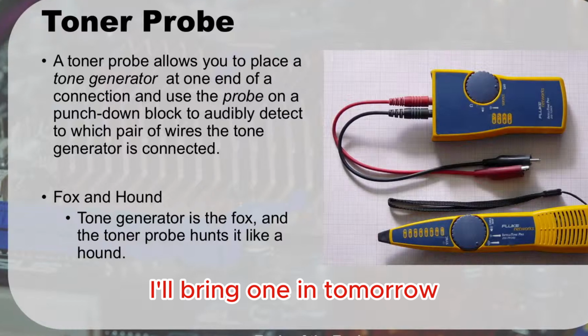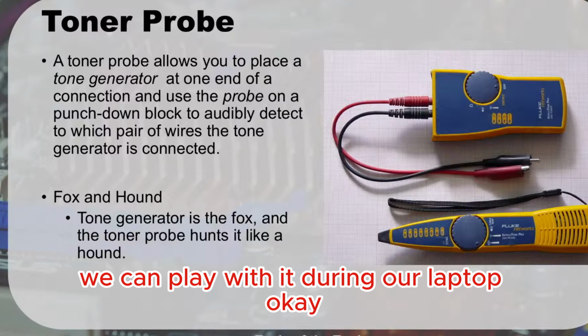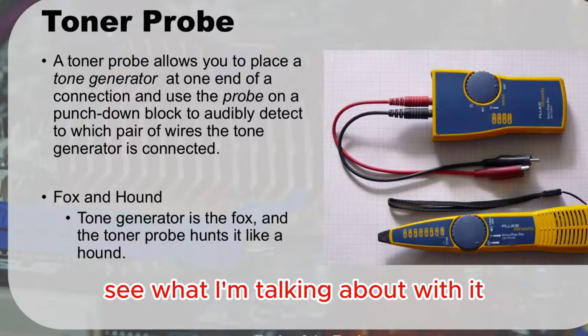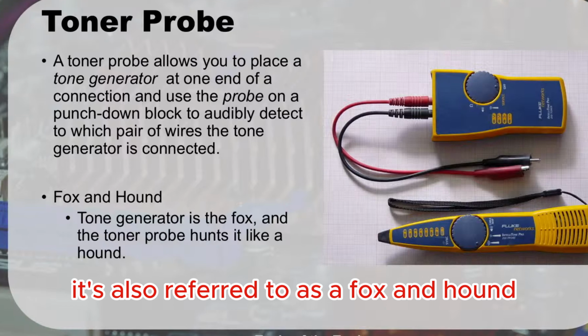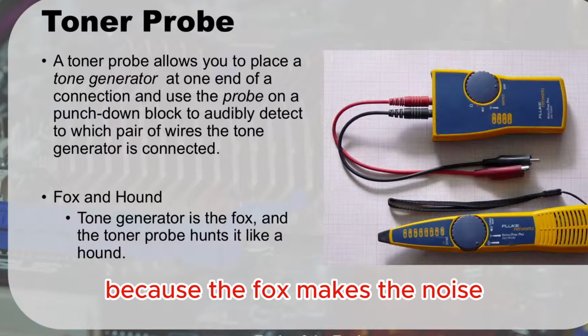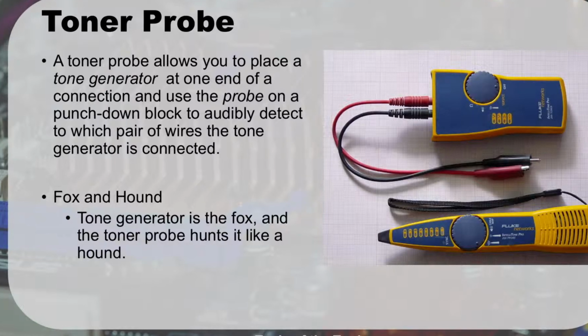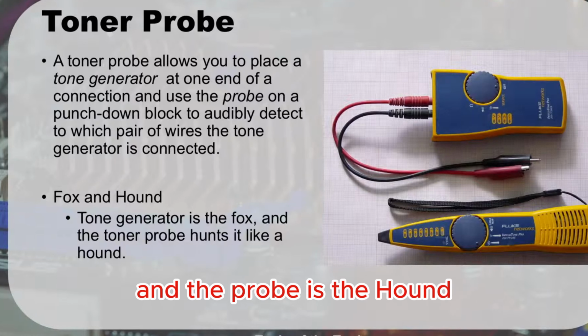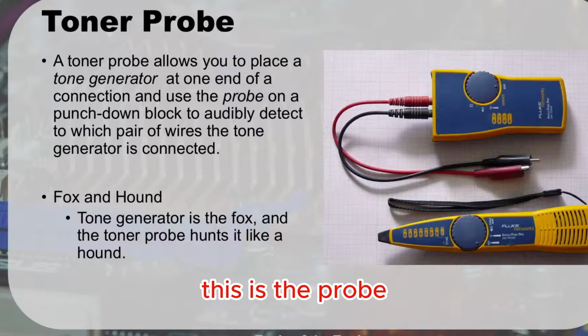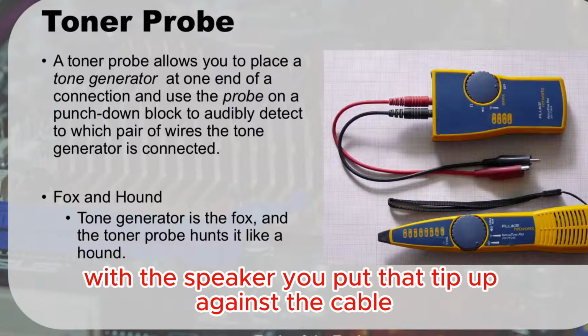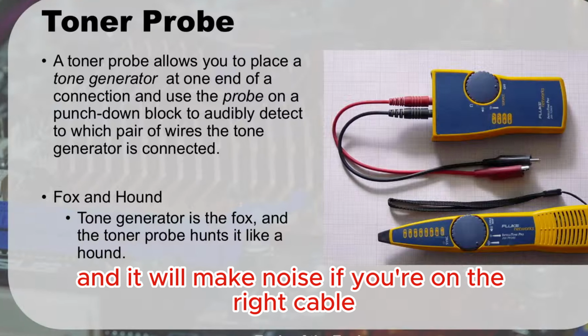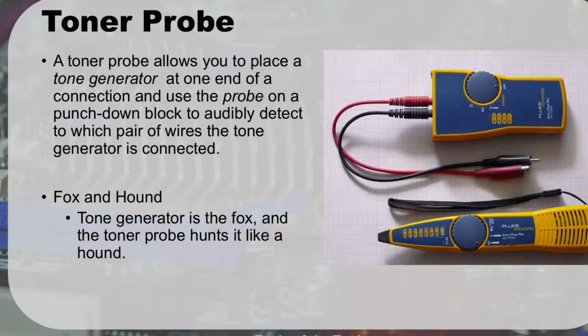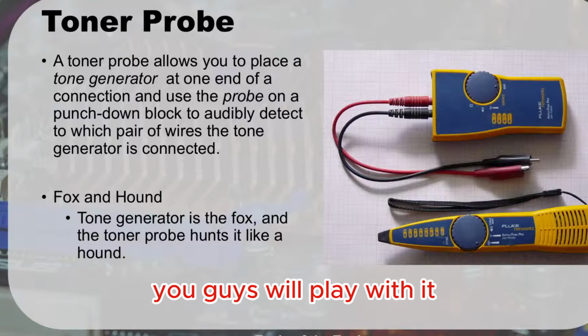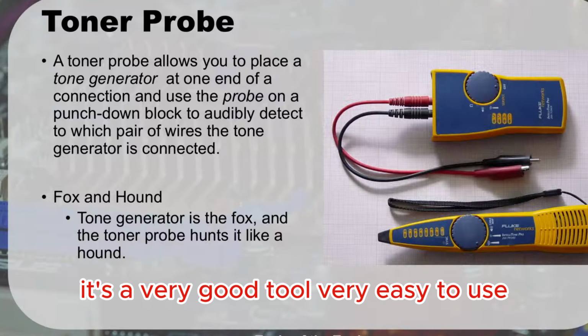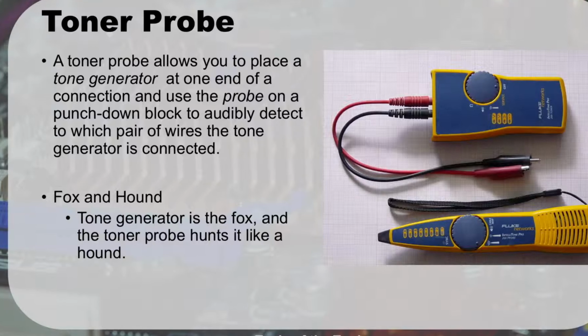I'll bring one in tomorrow so you guys can play with it and see what I'm talking about. It's also referred to as a fox and hound, because the fox makes the noise and the hound chases the fox—the tone generator is the fox, and the probe is the hound. This is the probe, the one at the bottom with the speaker. You put that tip up against the cable and it will make noise if you're on the right cable. Like I said, I'll bring one in tomorrow so you can play with it. It's a very good tool, very easy to use.